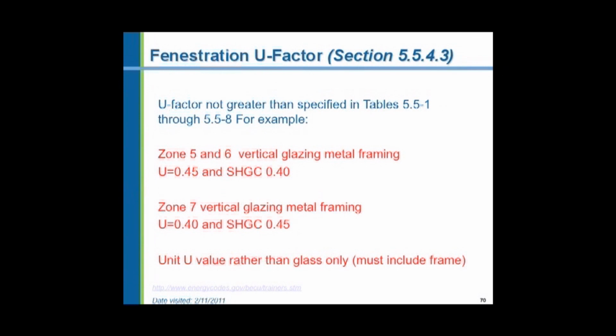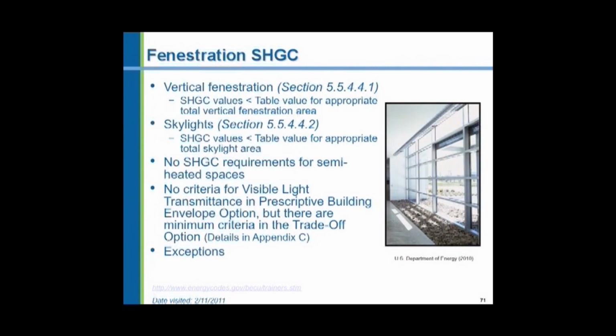And the maximum fenestration U value for metal frame windows in climate zone 5A is 0.45 and the solar heat gain coefficient is 0.4. And again, zone 7, the Upper Peninsula, 0.4 and 0.45. In many commercial applications, you will find a coated glass, a colored glass, a reflective glass. And these are metallic coatings that are applied to reflect sunlight and reduce heat gain. They can affect visible light transmittance, and they can also obviously affect the size of the air conditioning system. So solar heat gain goes right along with the heating and air conditioning system.